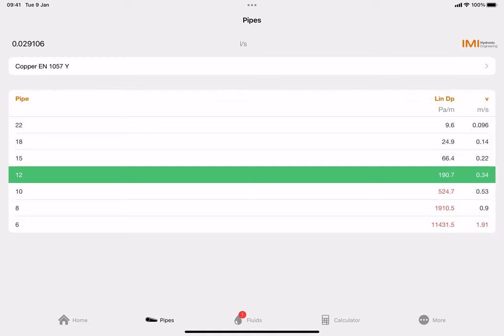It's still only 0.5 meters per second - still nearly half of our target velocity. Personally, looking at that I would be looking at 10 millimeter copper, and if it's not a very long run - say three meters to the radiator and three meters back, six meters total - we would be looking at 524.7 pascals times six because of the six meters, and that would be your total pressure drop. I want to quickly talk about pascals and kilopascals before we move on because this is where people get quite confused.